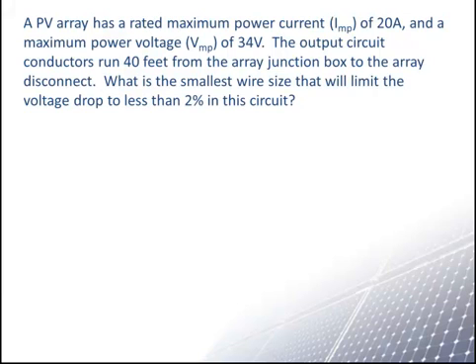A PV array has a rated maximum power current I_MP of 20 amps and a maximum power voltage V_MP of 34 volts. The output circuit conductors run 40 feet from the array junction box to the array disconnect. What is the smallest wire size that will limit the voltage drop to less than 2% in this circuit?